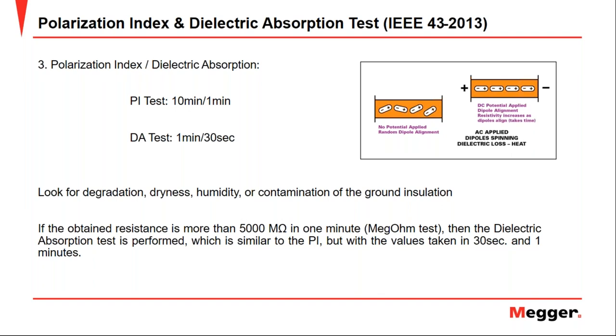Let's now go on to the PI or DA test. In this test, we're checking the ability of the insulation to polarize, to make sure that each insulation dipole can align correctly with the field. This is only possible if the insulation material is not dry, cracked, contaminated, or wet. Now, how do we know if we are going to perform the PI or the DA test? The IEEE 43 standard establishes that if the insulation resistance measured in 1 minute is greater than 5,000 megohms or 5 gigohms, then we must do the DA test. If it is less than 5,000 megohms, then we must perform the PI test, no matter the motor size.